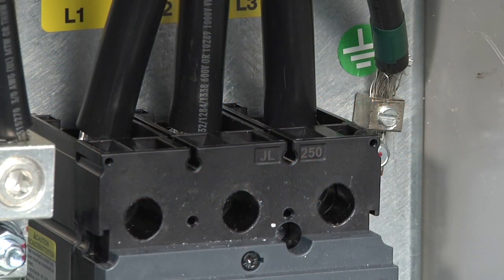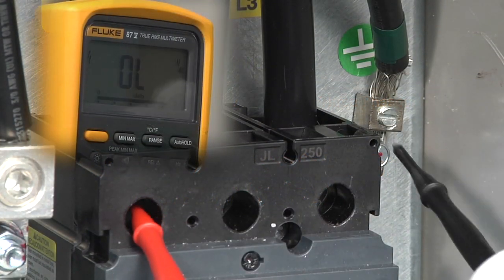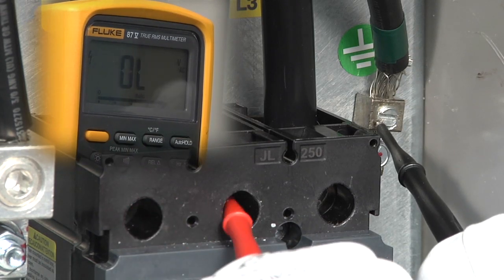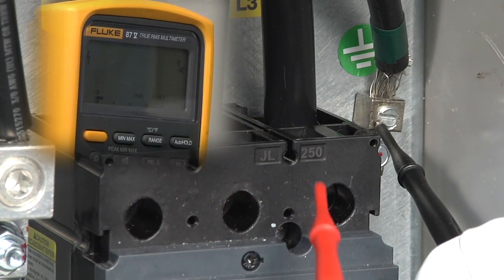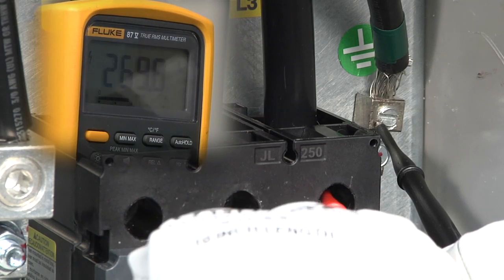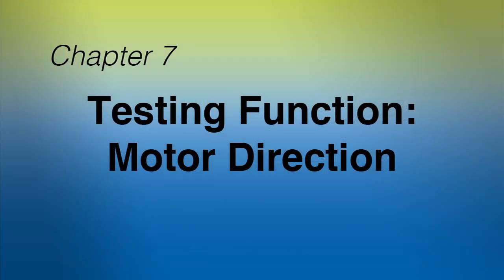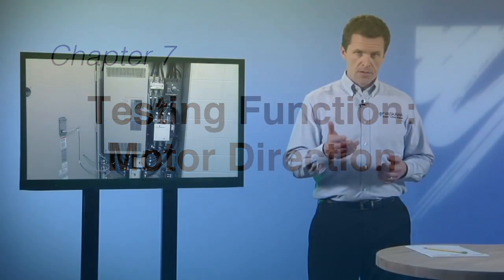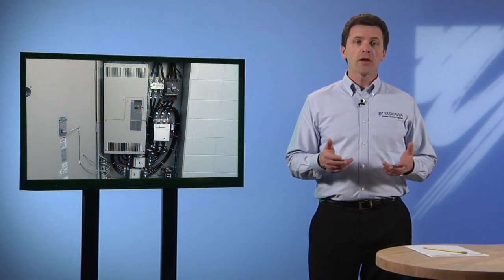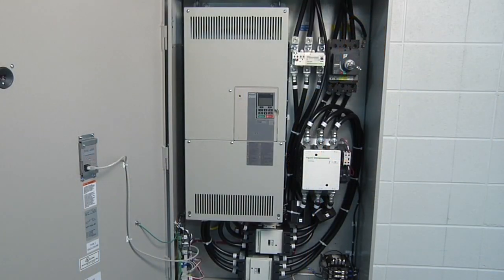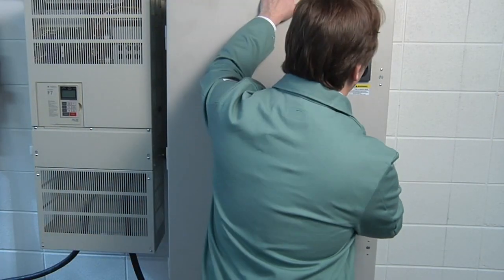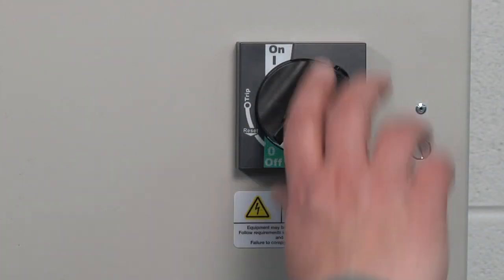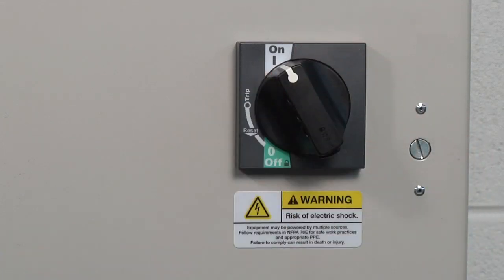In much the same way, we'll check phase to neutral, L1, L2, and L3 to ground. Of course, these measurements only apply to systems that have a true neutral. When the measurements are complete, we're ready to put the drive and bypass into operational mode. Close the door and secure it. Then activate the rotary switch on the front of the enclosure to close the circuit breaker.